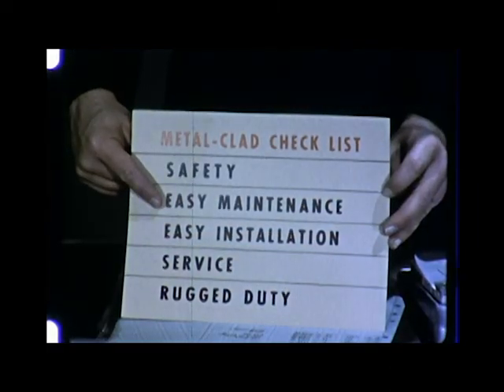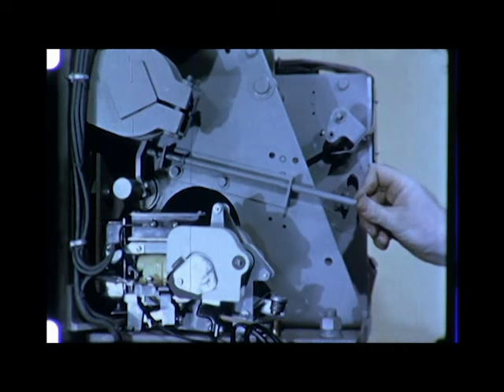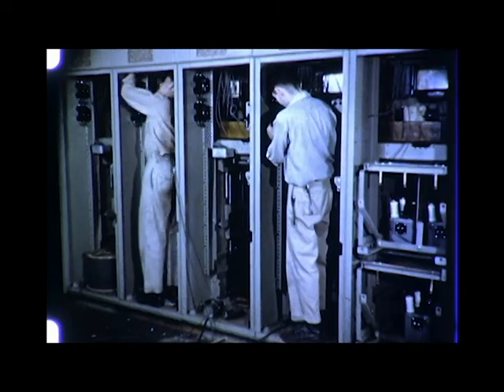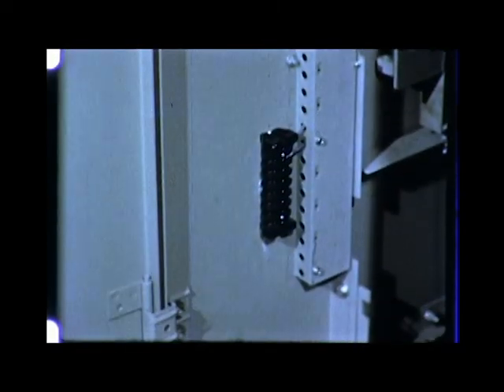The next point was easy maintenance. This equipment is built to last, to offer many years of effective service, but if and when maintenance is necessary, the job is easy. And as far as the Magne-Blast breaker is concerned, one man can do it. Another point was easy installation. Compact design saves valuable space and makes metal clad easy to install. Our switchgear is delivered in as large sections as shipping limitations will permit. Impact tests have shown that the all-welded steel construction of metal clad helps it withstand the jolts of cross-country travel. Sections are completely preassembled with interconnections made and control devices in place and wired. After the sections are installed, the adequate space provided makes it easy to install incoming and outgoing cables. Equipment is completely wired at the factory, with wiring brought out to convenient terminal boards, and provision is made in advance for all the purchaser's connections.